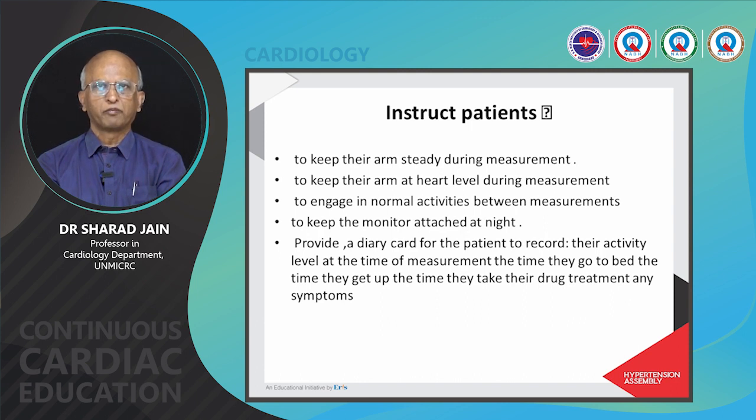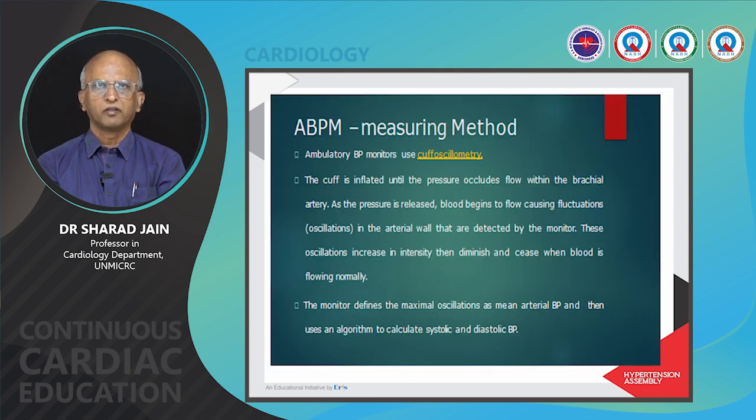When the BP starts inflating, you have to keep the arm steady, at heart level during measurement, to engage in normal activities between the measurements and to keep the monitor attached at night. Provide a diary card to the patient to record their activity level at the time of measurement, the time they go to bed, the time they get up, and during drug treatment, etc.